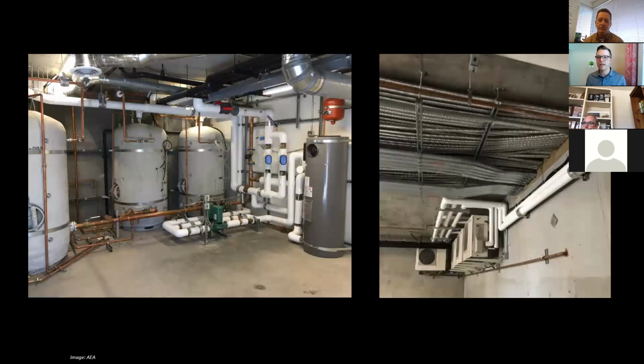Moving to another system, this one looks a bit more complicated but is actually pretty simple in how it operates. This system uses smaller heat pumps, originally designed for residential use, like you see on the right-hand side, that use CO2 as their refrigerant. It takes four of those small heat pumps and connects them to one of these large tanks, so each large tank on the left-hand side is connected to four small heat pumps. This gives a lot of redundancy and allows a lot of flexibility in terms of meeting the load.